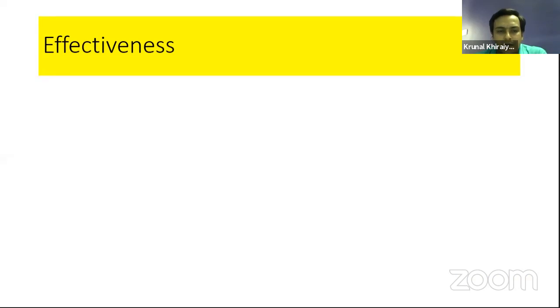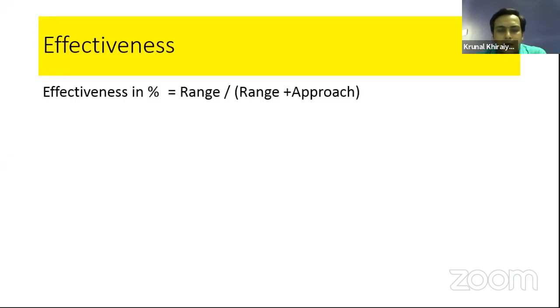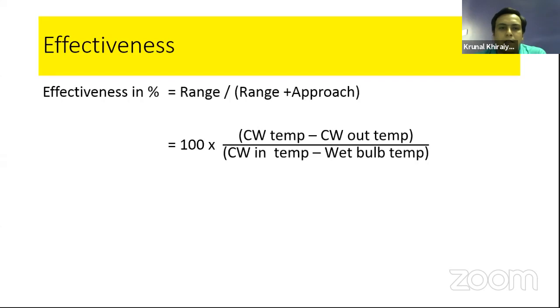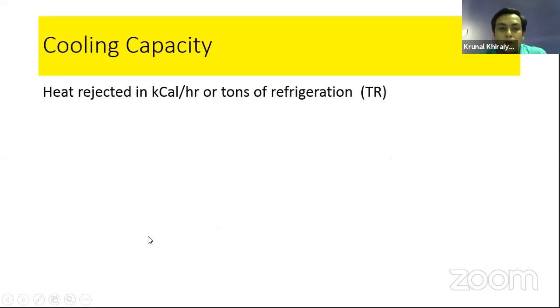Now effectiveness. Effectiveness is always expressed as a percentage. It is equal to the range divided by the range plus approach. Audience, please be ready, knowledge checks are coming. So you can have a percentage, which means 100 times range divided by range plus approach. And here we have the conclusion from the effectiveness calculation: high effectiveness indicates good performance.